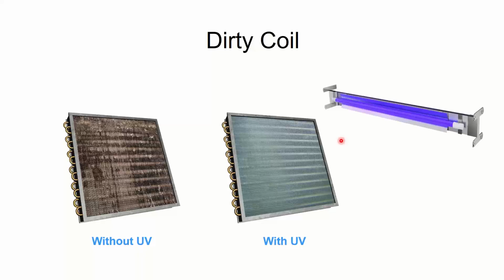So I have all the shine time that I need is available to me. So it keeps fixed surfaces clean like evaporator coils and condensate pans. It's really good for that. It is not good for cleaning air. We've been saying that for at least 15 years that I've been doing training over here. Don't put UV lights in to clean the air. Put UV lights in to clean the coil.